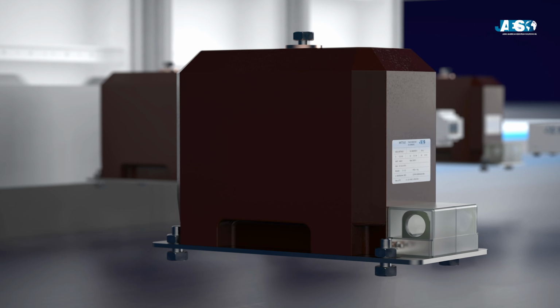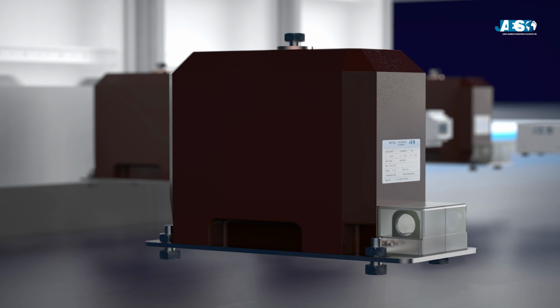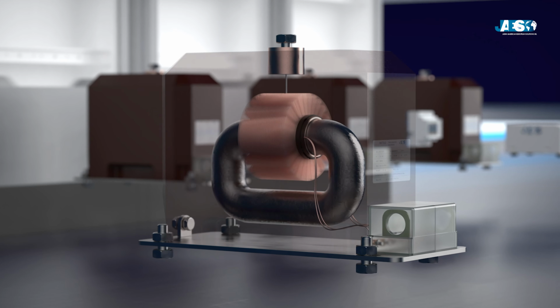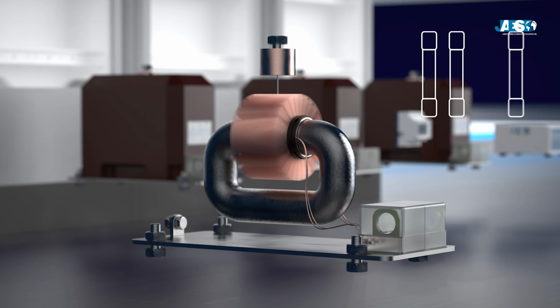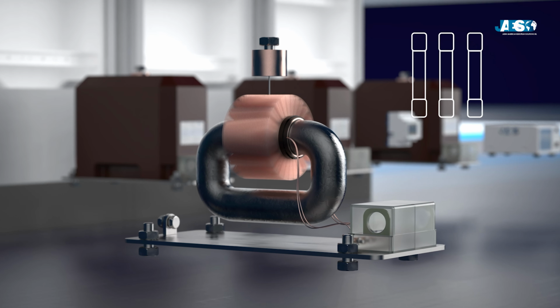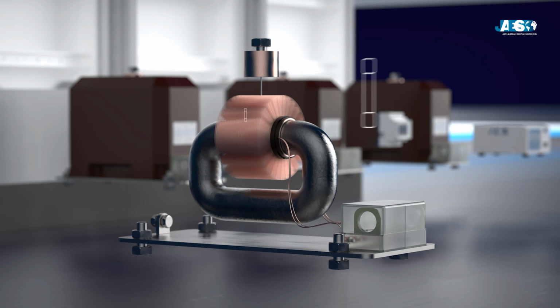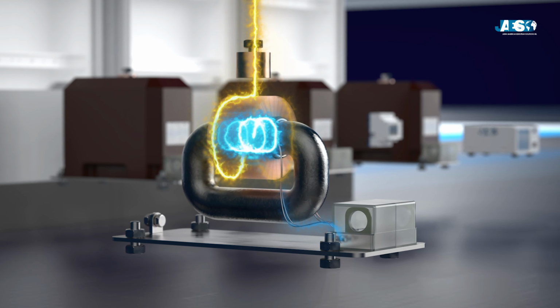The VT is characterized by an apparent power that must never be exceeded. To avoid damage, it is equipped with protection fuses connected in series to the primary circuit, which have the task of limiting the maximum current that can circulate within it.